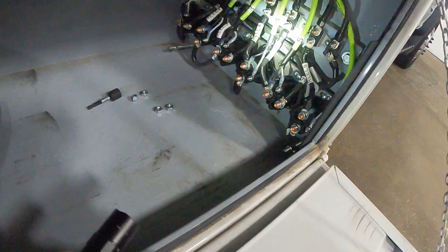There are individual buttons on top of these breakers, so if for whatever reason one of your reels fails, pull this cover off and make sure that circuit breaker is not tripped. If it needs to be reset, the button will stick up and you can just push that button back down and it will reset. Obviously, if there's a problem within the wiring, the motor, or something like that, and the circuit breaker doesn't reset, you will need to troubleshoot further.